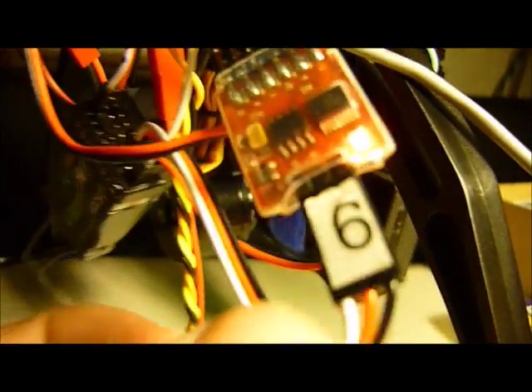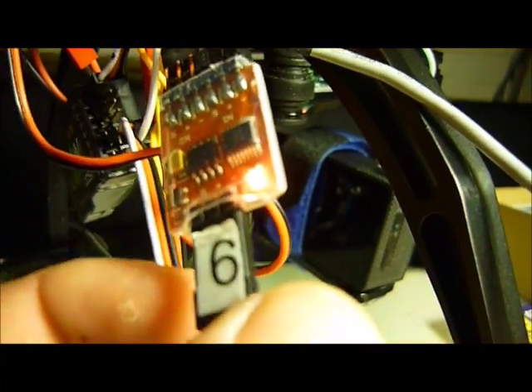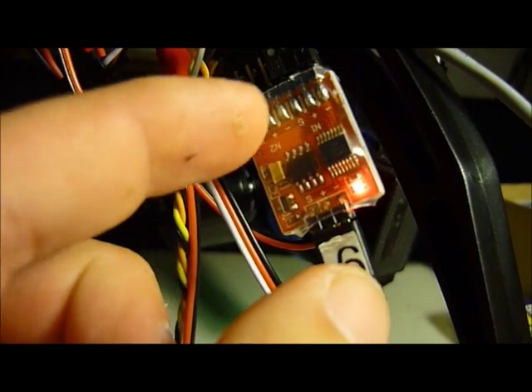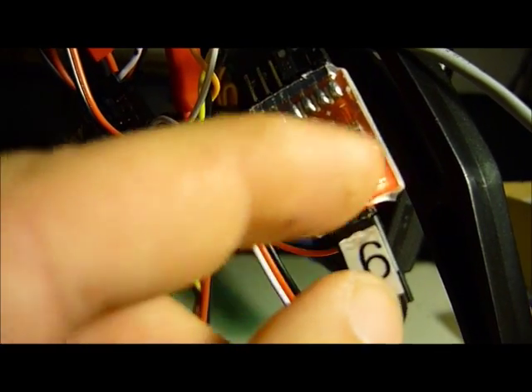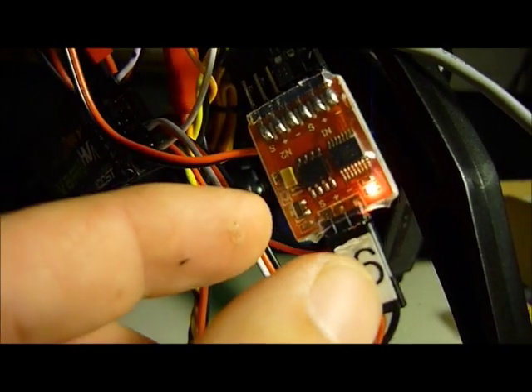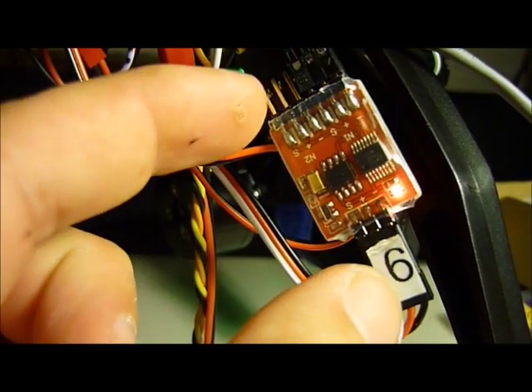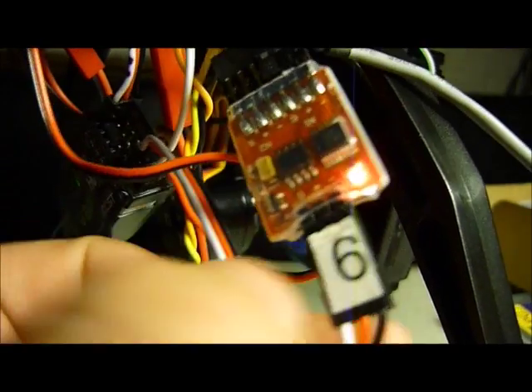What I was doing wrong was I was assuming that the five volts fed from the receiver would power the cameras also. I thought it would go right through the board, but it doesn't. It's isolated. So basically, these are all dry contacts.